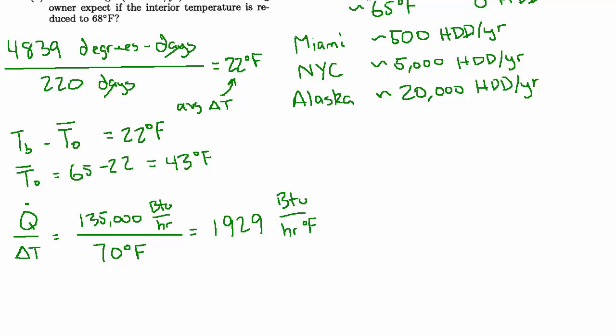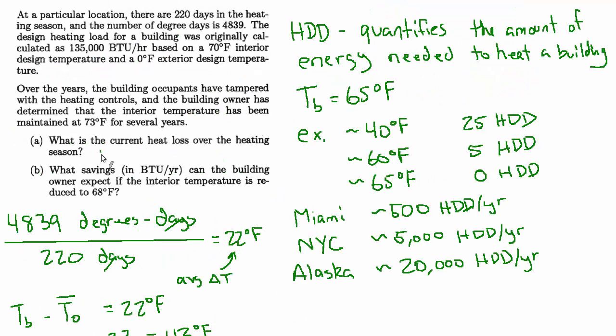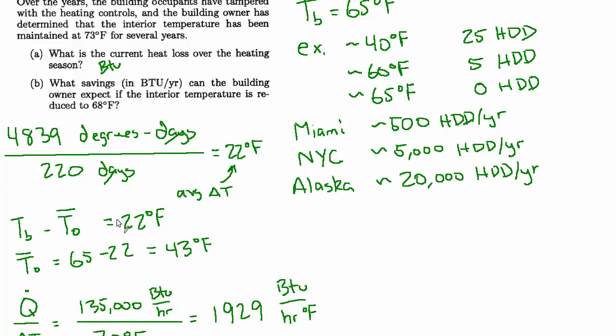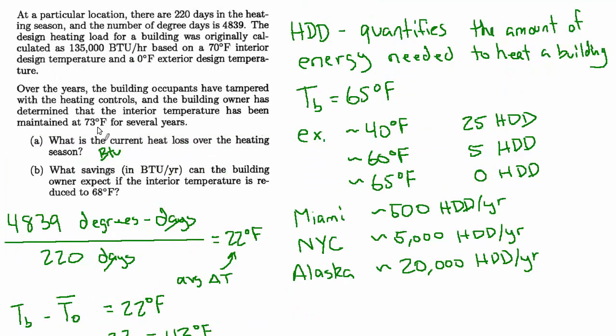So if we want to calculate the total heat loss, as they're asking us to in part A, we want an answer that's just BTUs. We want to know the total amount of energy. So we can use this number, which is energy per unit time and per degree F, and just multiply by the delta T and the amount of time in the heating season. And we should get the total heat loss. So the total heat loss is going to be 1929 BTU per hour per degree Fahrenheit times the actual delta T. And now this is going to be based on the actual operational conditions. So unlike when we're talking about heating degree days, and we use this base temperature, now we want to use the temperature of how they're really controlling the building.